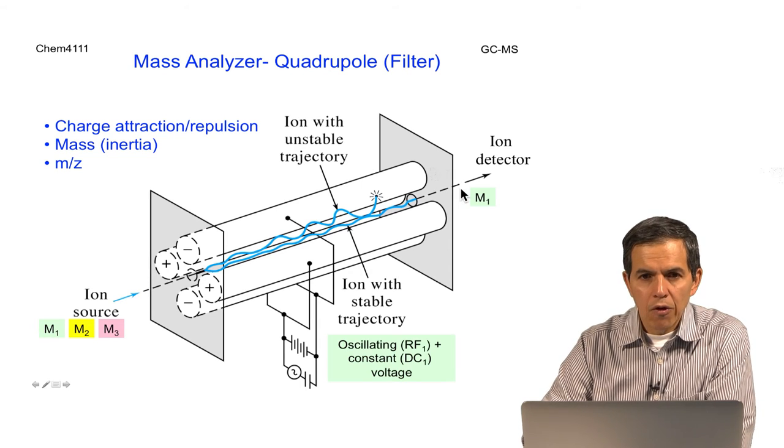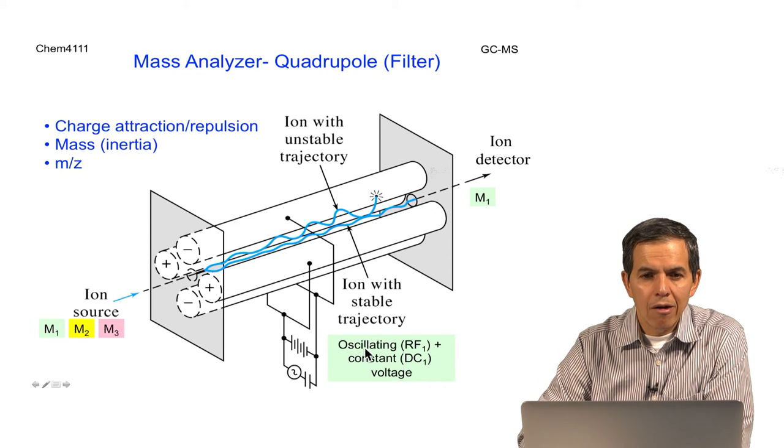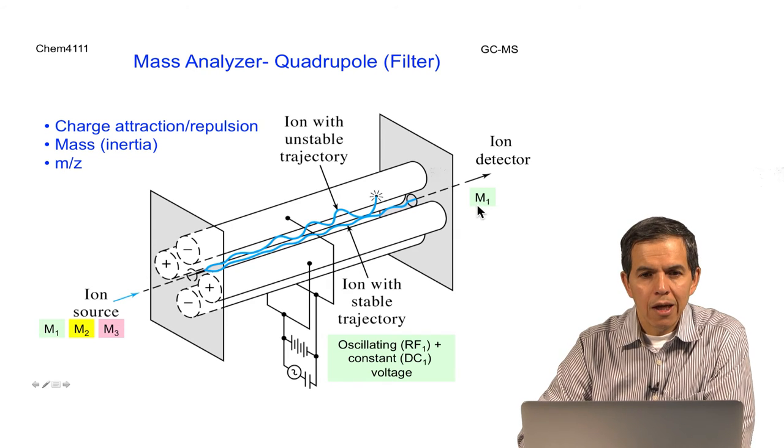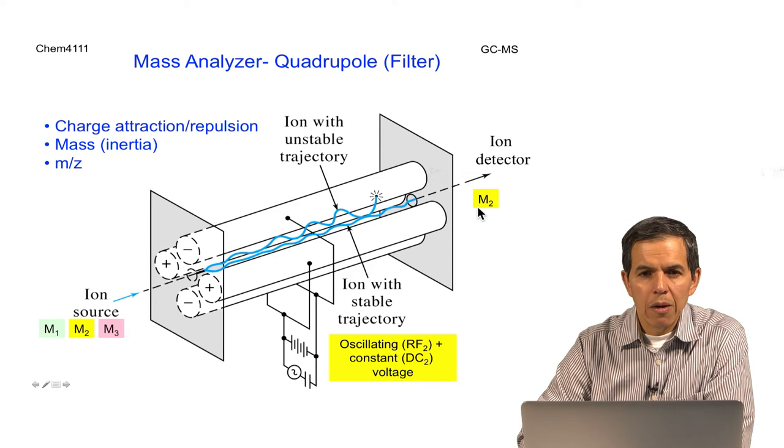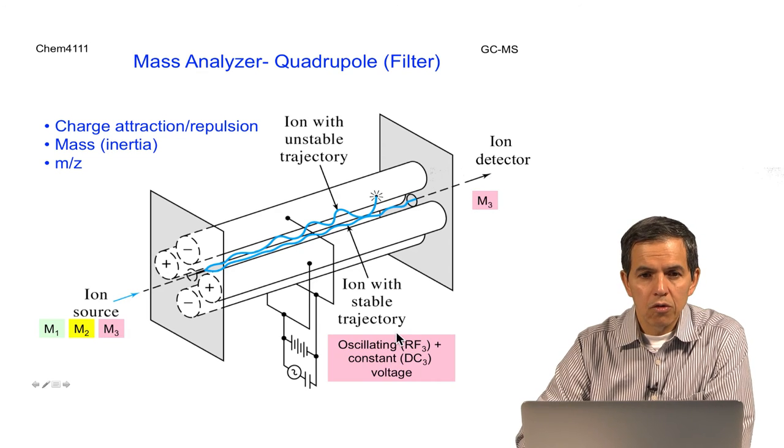However, some ions might be able to make it all the way through the quadrupole system towards the ion detector zone. If we have a correct selection of the RF and DC voltages, we might be able to select ion M1. Similarly, if we select different voltages RF2 and DC2, we might be able to select ion M2. If we change the voltage to RF3 and DC3, we might select ion M3.